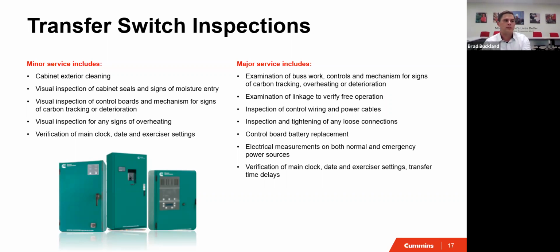I like pointing this out because there's a bigger issue with the industry switching toward a safety protocol put into place a couple years ago, which has been transitioning into planned maintenance work. These ATS units have constant utility feed from power coming in, and it's kind of semi-exposed. So if any dust or debris gets in, or it sparks, something called an arc flash can come off - it's an explosion that can kill people, and it's very hazardous.